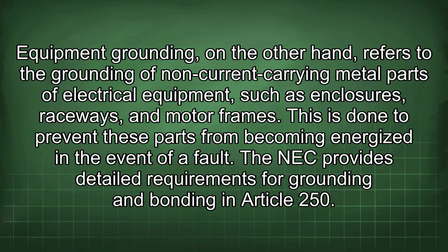Equipment grounding, on the other hand, refers to the grounding of non-current carrying metal parts of electrical equipment such as enclosures, raceways, and motor frames. This is done to prevent these parts from becoming energized in the event of a fault.